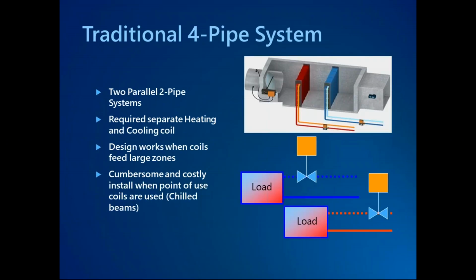So first and foremost, before we talk about what a six-way is, we need to understand the type of system that these are being used for. I'm sure most people are familiar with what a four-pipe system is, but just to review, it's two completely independent heating and cooling systems within the building. This four-pipe system traditionally requires two independent coils, one for heating and one for cooling. These coils are going to be in the airstream. What you're seeing in that top picture there is a traditional fan coil unit.